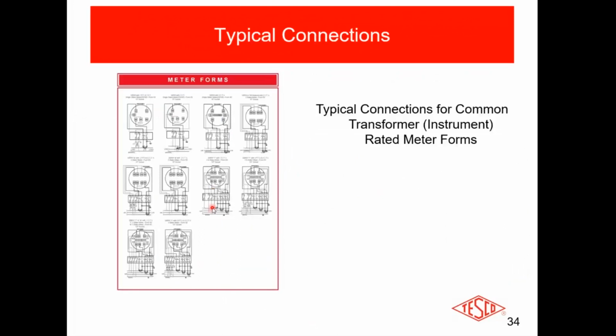Meter forms. There are a lot of meter forms, and they are constantly adding more. At some of our ANSI meetings, there are actually petitions within the last couple of years for new and different meter forms. Most utilities probably don't use more than 20 meter forms. Some use less than that. Many use less than that. But there are many different meter forms used for a variety of different reasons, for a variety of different services. So depending on the service and what you're trying to do, you may have a very good reason. You typically do have a very good reason as to why you would pick a particular form. There are lots of different ways to skin the cat. You can appropriately meter a single installation with a whole wide variety of different meter forms if you wanted to. A lot of it goes back to what does your utility like to do? What does it typically do?